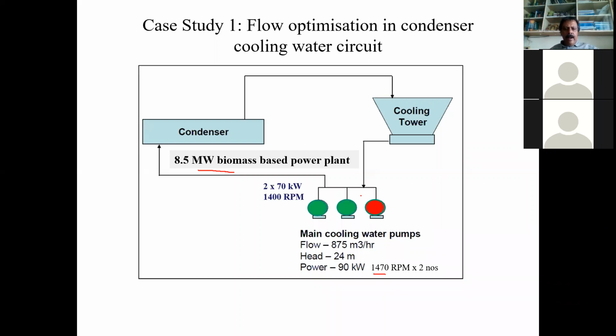Now, the company had a VFD for these pumps. We are operating two pumps now. The original RPM is 1470, and now we are operating at 1400 RPM. At 1400 RPM, the pump is drawing 70 kilowatt. The important thing when you're operating these two pumps with the VFD is that both pumps should operate at the same speed.